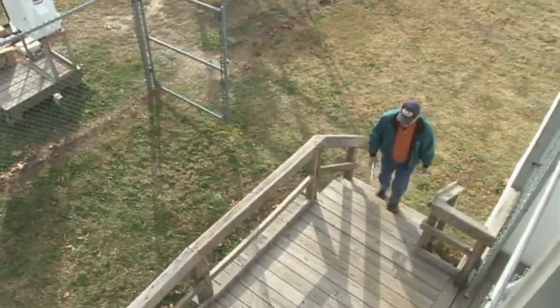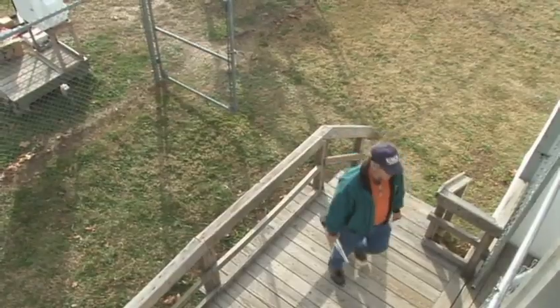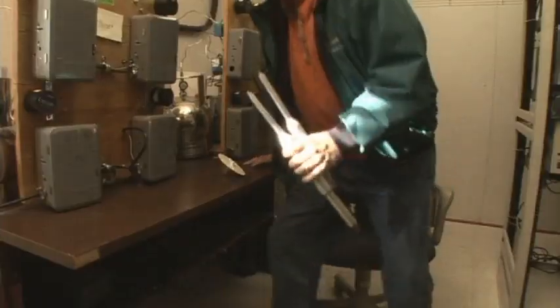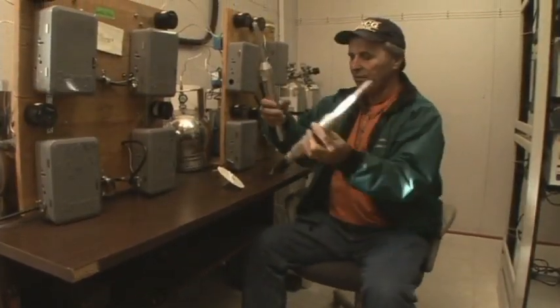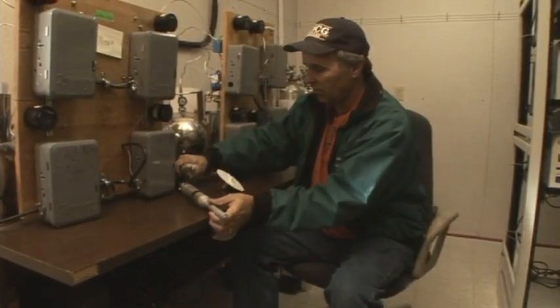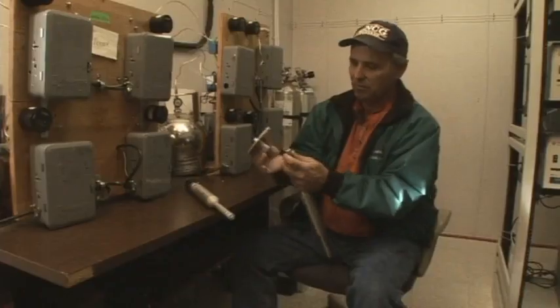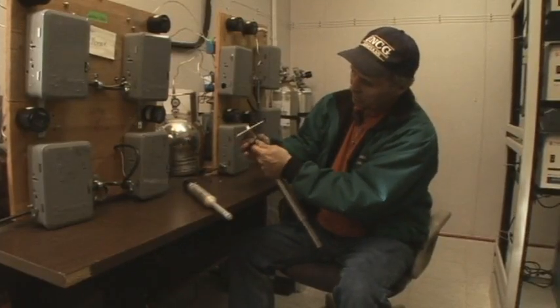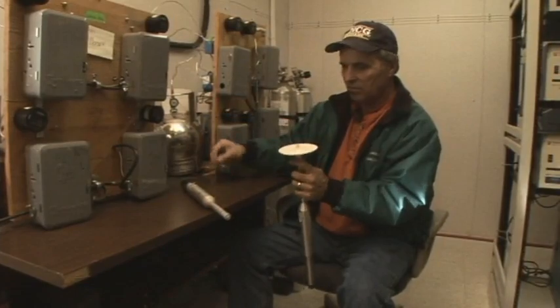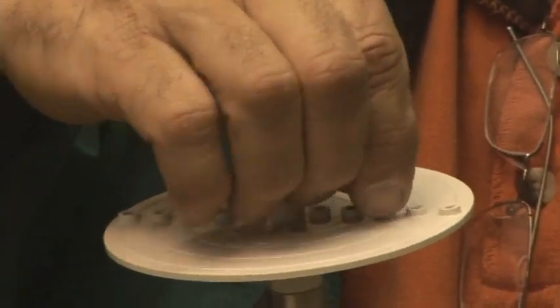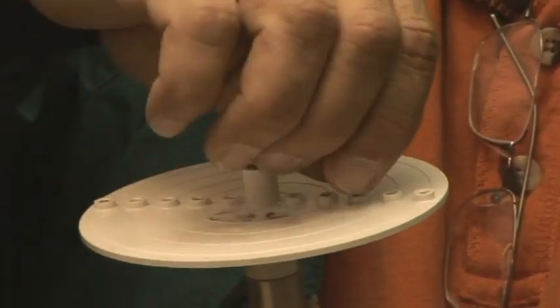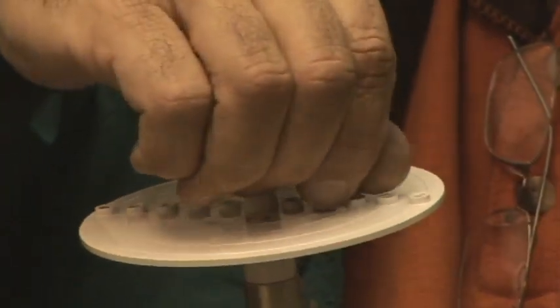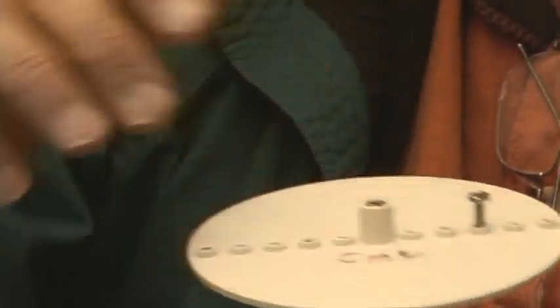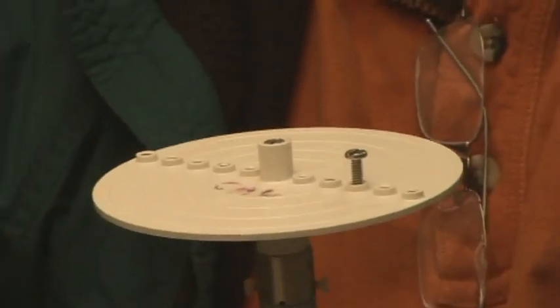The torque test is performed by removing the sensor from the tower and bringing it into the shelter. On a flat surface, place the sensor upright on the bench. Attach the torque wheel to the shaft of the sensor. A grommet or small piece of tubing can be used to make a snug fit. Now that the torque wheel is attached, place one of the screws in the middle hole on one side of the wheel. With the 1 gram screw in the third hole, gravity generates 3 gram-centimeters of force, or torque.